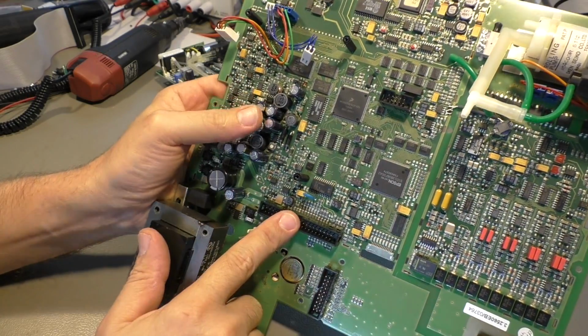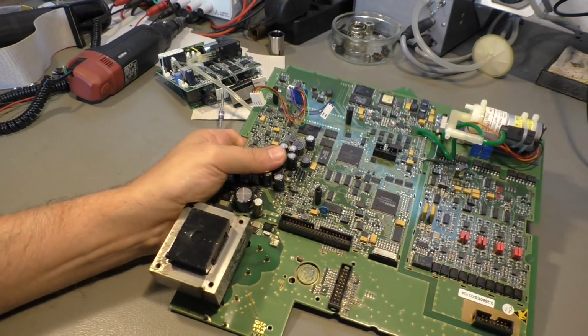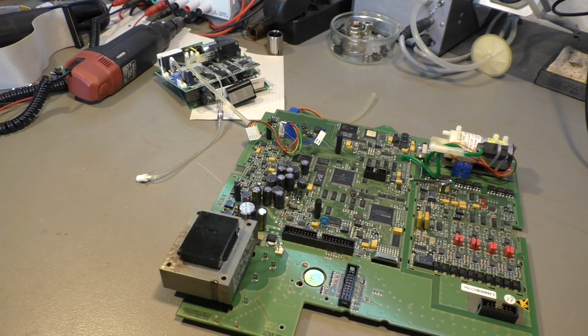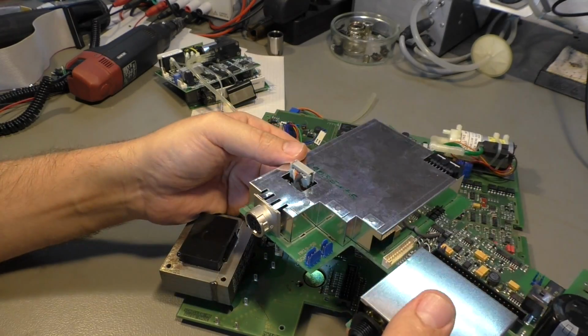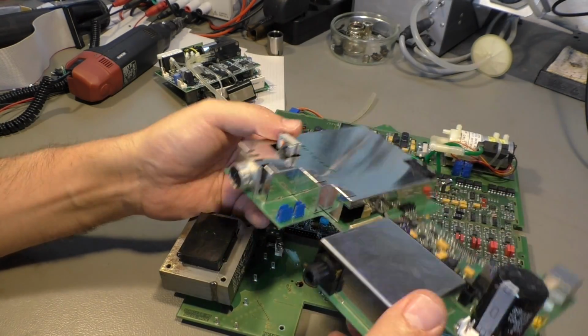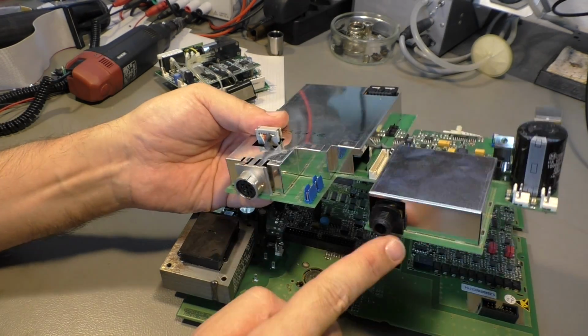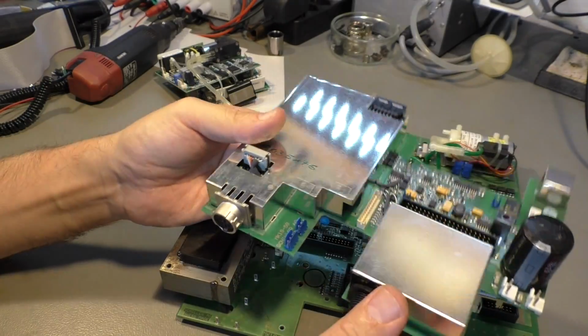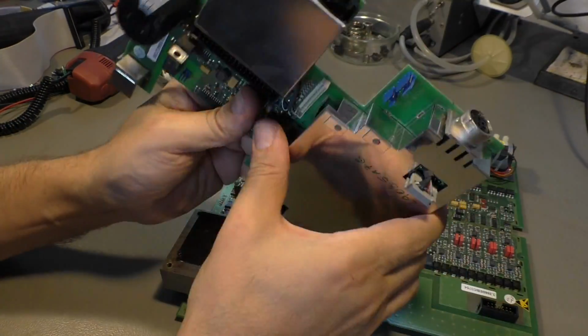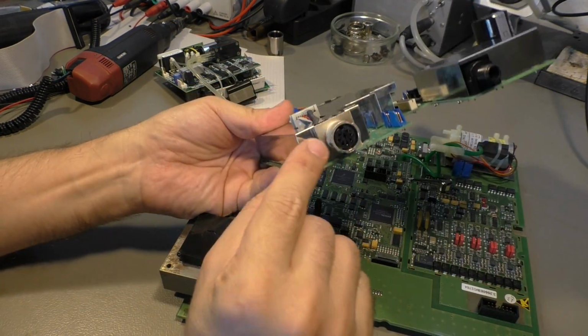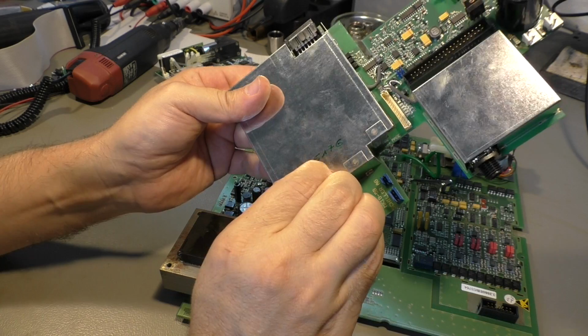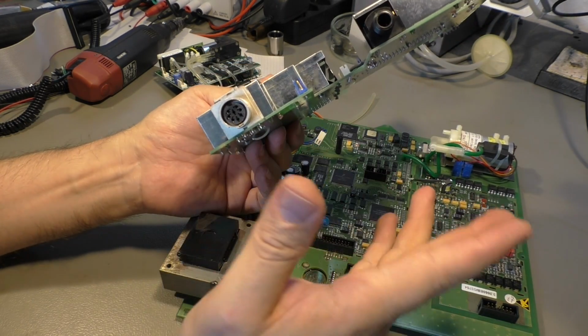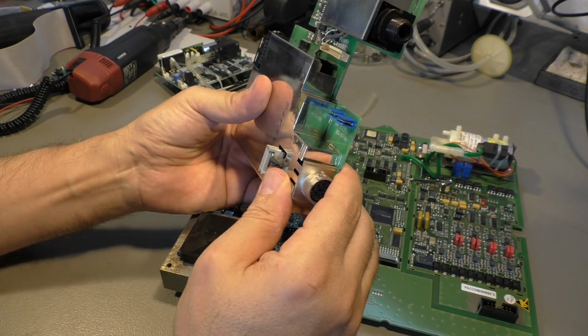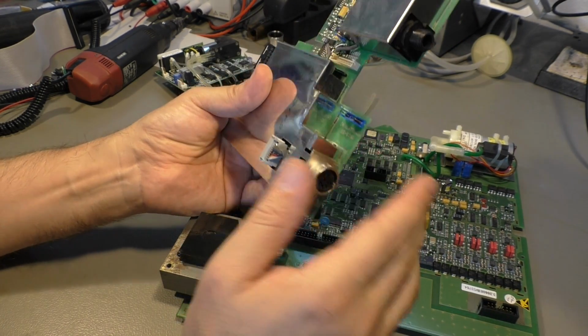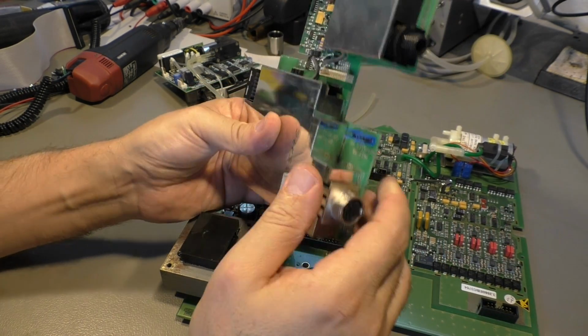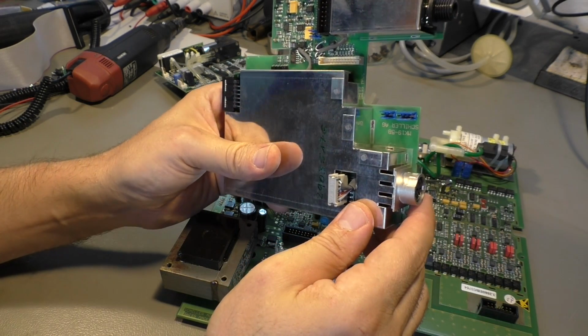That's the plug that goes to the unit that still is here in the back. That's the SpO2 measurement unit, and also where the temperature sensor goes. This is also an option. You can have different options of measurement methods here. So the SpO2, that's the saturation of oxygen in the blood. So normally if you are a healthy person, you have something between 90 and 100%. If you're not working extremely hard or holding your breath for a minute or two, you shouldn't do that.